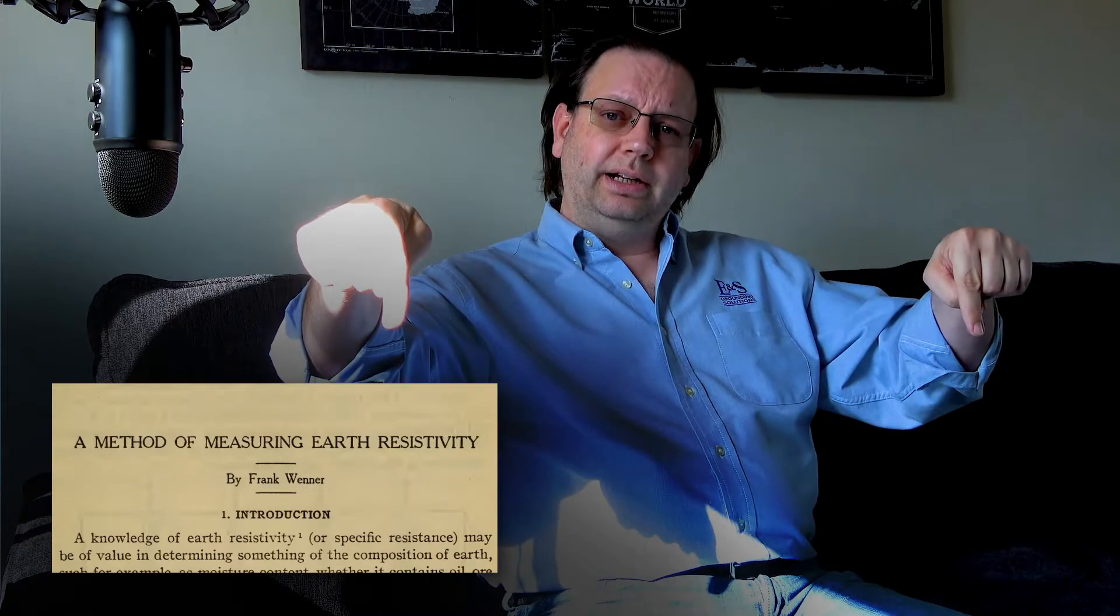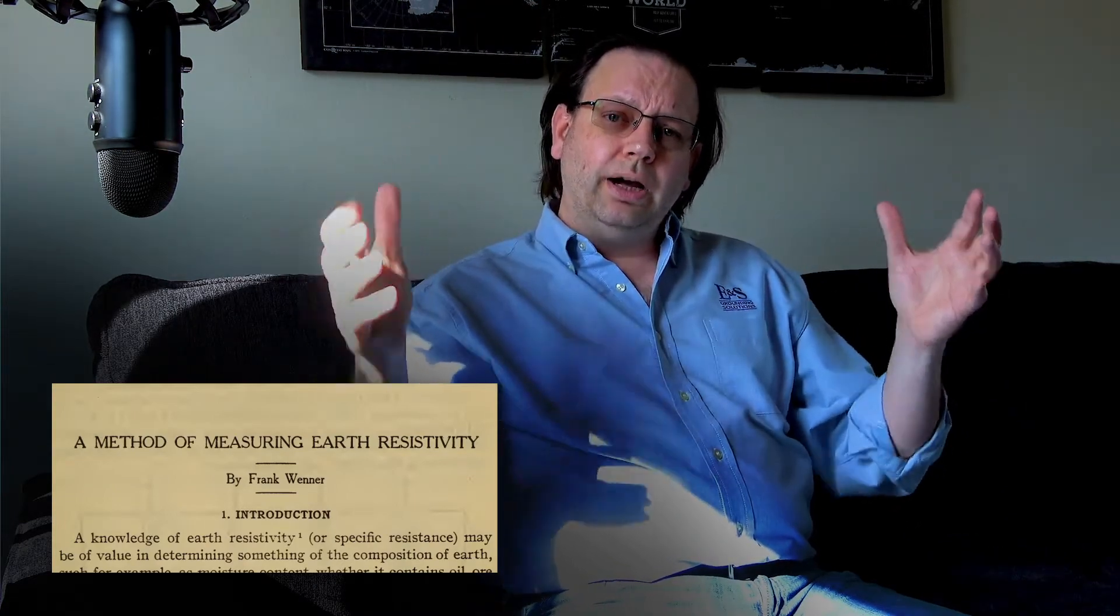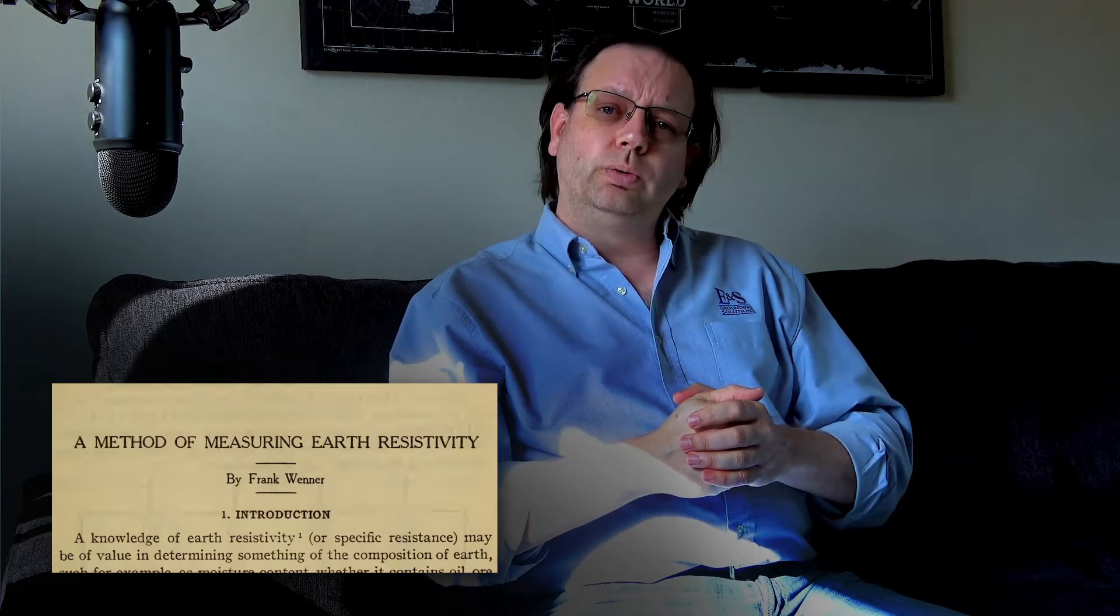This guy Wenner back in, I want to say it was 1906, 1901, oh forgive me guys, way back at the early turn of the century, he wrote a paper where he discovered that if he placed the current probes on the outside and the voltage probes on the inside, he could measure down into the earth and get an average soil resistivity. And what he found out was he wanted equal spacing. So if he placed the probes at five foot spacing, he could actually measure down into the earth five feet into the earth.